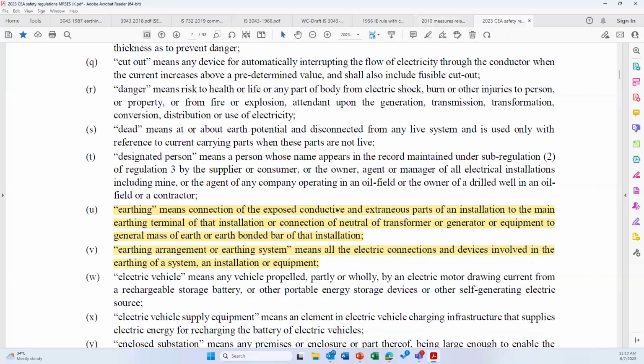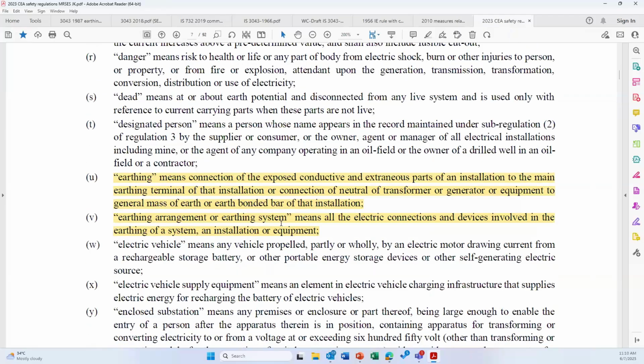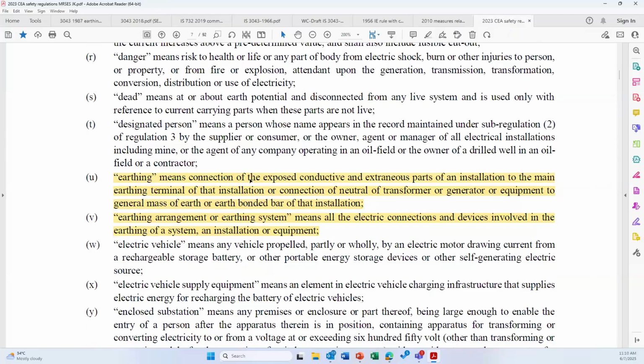Similarly, in 2023, there was a big change. The 2023 CEA regulation has changed the definition. I don't know how many of you have really noted it down. Here, there was no definition of earth or earthed; the definition of earthing was given. Earthing means connection of exposed conductive parts and extraneous conductive parts of the installation to the main earthing terminal of the installation. That means in a building, your exposed conductive parts and extraneous conductive parts are connected to the MET, one common bus bar, or connection of the neutral of a transformer or generator or equipment to the general mass of earth, depending upon the situation.